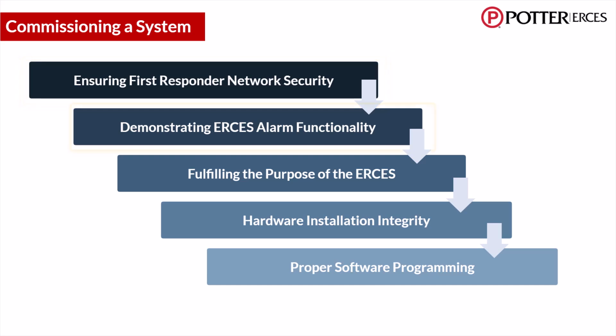They are also responsible for demonstrating that the alarms and safeguards in place are working and activating properly. Along with network protection and alarm demonstration, the commissioning party must show that the ERCES is providing signal in 99% of the critical areas and 95% of the general areas of the building. They must also ensure that the passive components and hardware have been installed per the AHJ's requirements. Finally, the commissioning party will be responsible for demonstrating that the BDA is properly programmed and supporting the frequencies utilized by the local first responders.